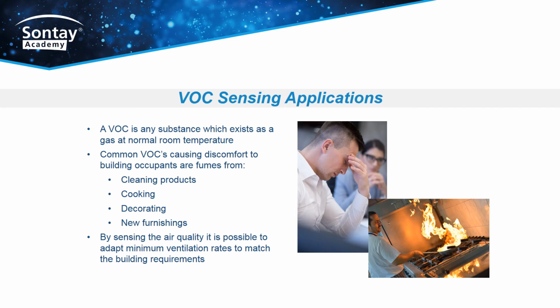Volatile organic compounds are not as menacing as the name suggests, and include any substance which exists as a gas at normal room temperature. Cleaning fluids are one of the most common sources of VOC in commercial applications, and by sensing the VOC level along with the CO2 level, the minimum operating speed of the fresh air plant can be adapted to operate at its lowest permissible level based on actual conditions.